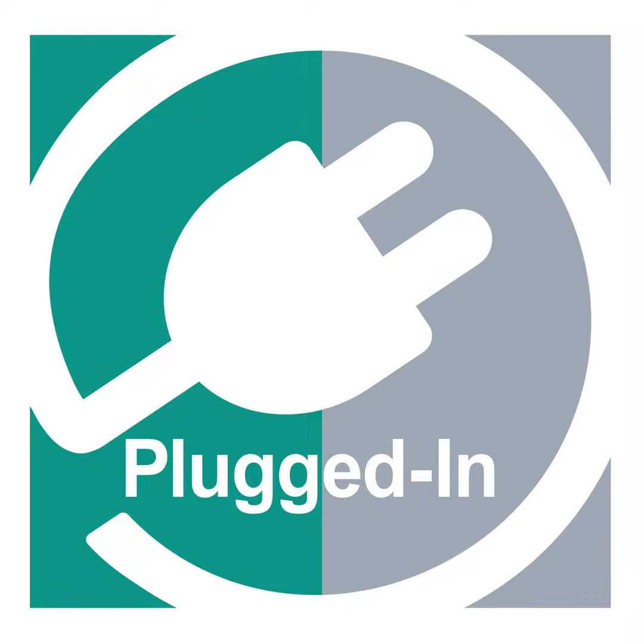That's right. So the PUR is used for some of the most challenging environments. And there are, sorry for interrupting, a couple of different variants that we should be talking about. That's right. So we have several different variants. The PUR-U, which has a UL approval, very highly flexible. A PUR-A, which is for automotive, very resistant to welding sparks for the automotive industry. PUR-O for the outdoor, very durable for outdoor applications.